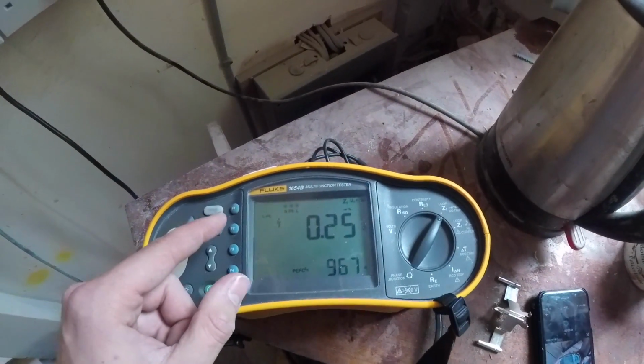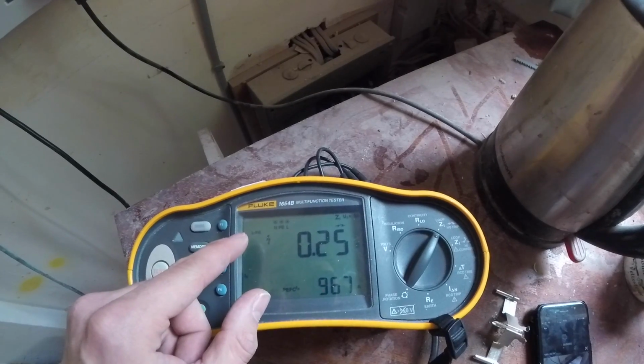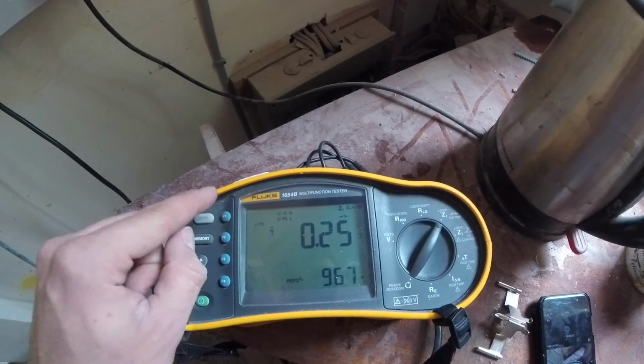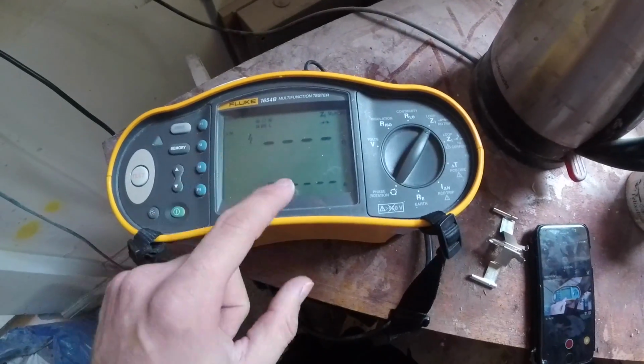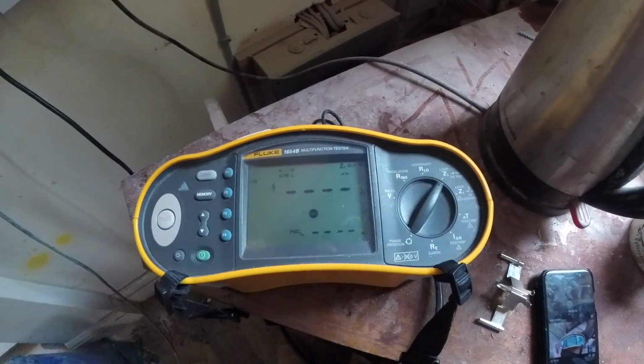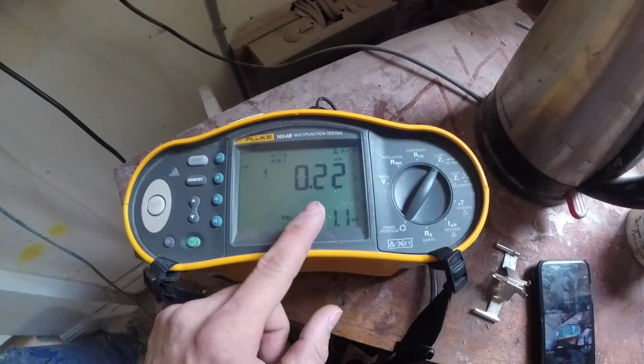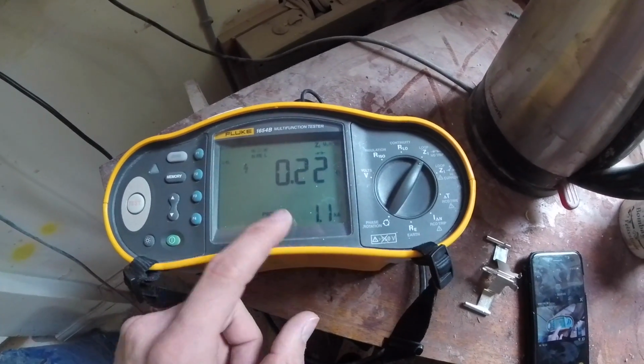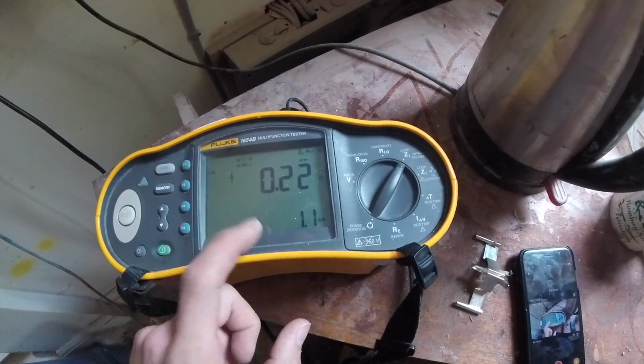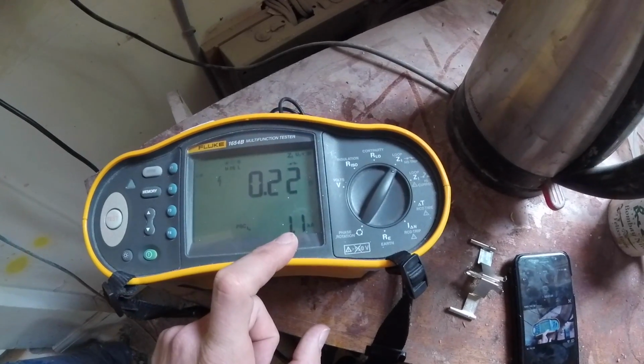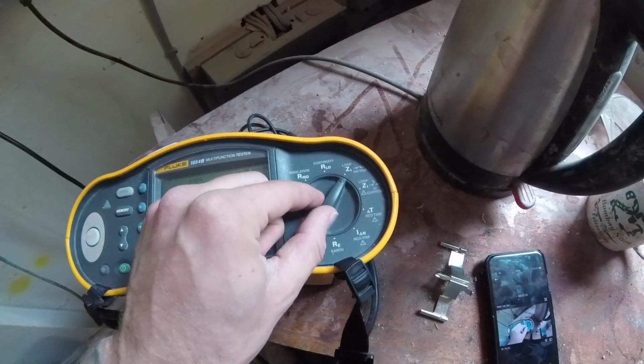If you want to measure between different conductors rather than the live to PE, you can actually do live to neutral, and then that'll give you your short circuit, prospective short circuit current down the bottom. So if we press test again, so that measures between live and neutral, but it does give you your short circuit, prospective short circuit current down there of 1.1 kA.